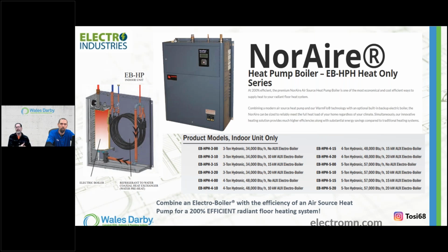So we have the refrigerant-based outdoor heat pump doing its job for 80-some, 90% of our heating load. Just in case it gets a little too cold out, pump that electric boiler a little bit, charge, boost the water temperature. Hey, it's getting so cold out, turn off the condenser and now go full boiler. Or, I don't want to buy this, I have something on the floor, I got plenty of life left: buy the NorAire without the boiler, use that fossil fuel now and off and go. Again, redundancy. I think it's going to be the future of modern day heating.